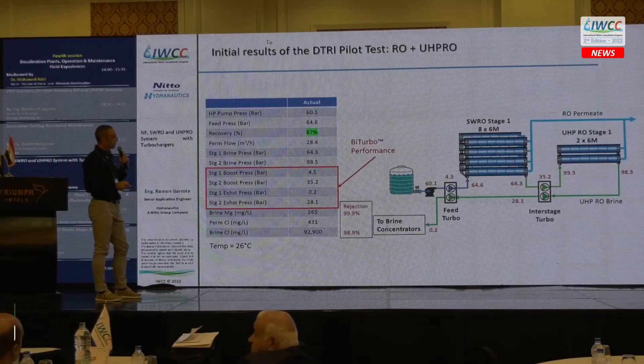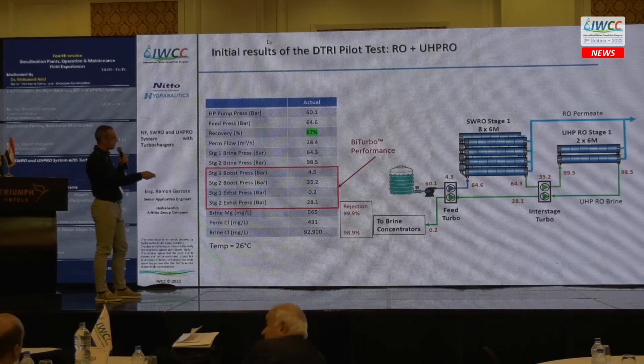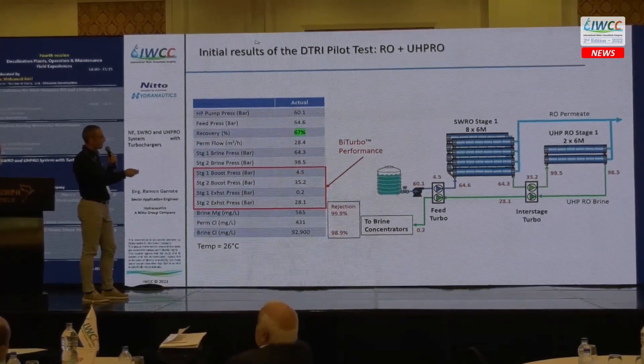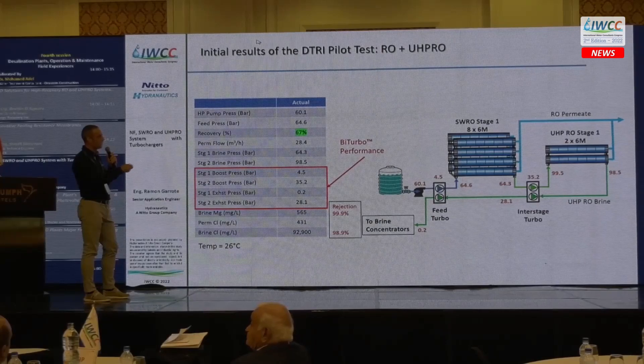For the RO system, we feed at 60 bar on the high-pressure pump, and the feed turbo provides approximately 5 bar more, so we enter the system at 64 bar. The interstage turbo then provides 35 additional bars, so we are feeding the ultra-high-pressure stage at 99 bar. Rejection for magnesium and chloride is 99.5% and 98.9% respectively.